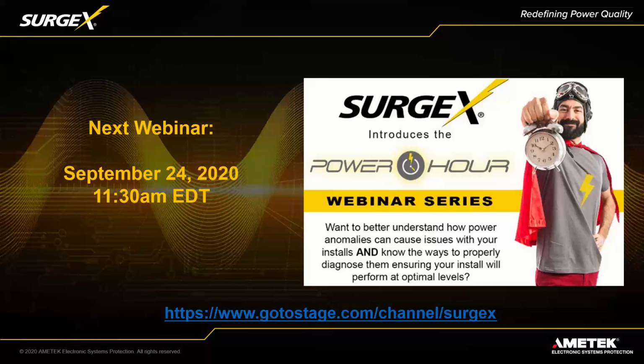When we see these logs, we invariably see that voltage fluctuation is a persistent, common problem all over the U.S. Jimmy, have you ever seen an Envision log where the voltage didn't vary to some degree? I think three times since 2014 we've been able to say there's no issue with the power. Do you remember one of those times? Yep, the voltage was between 120 and 121 for like 30 days.